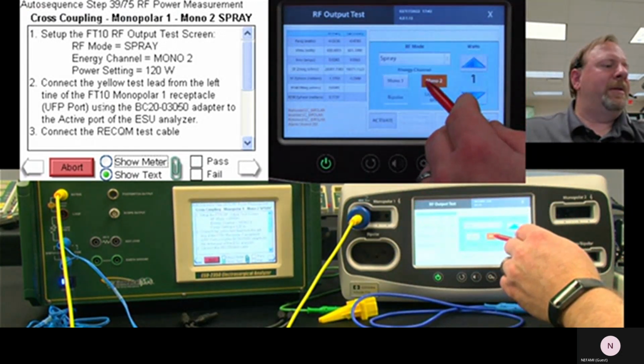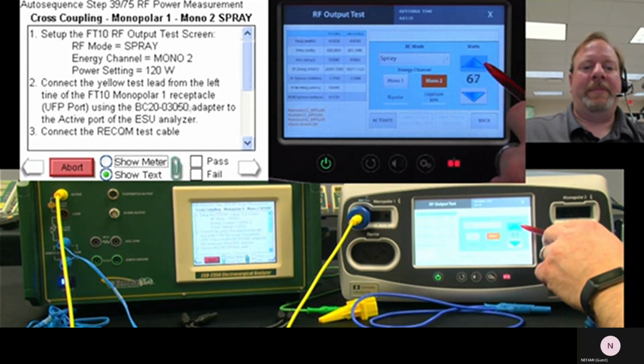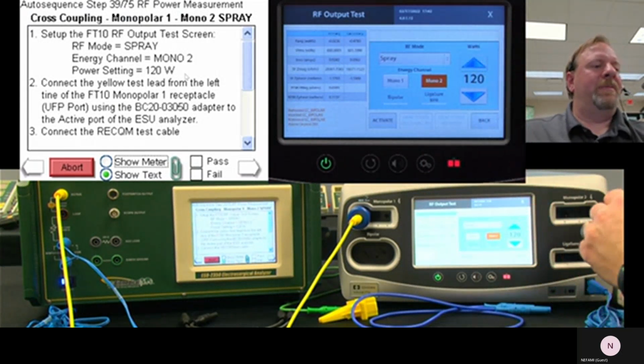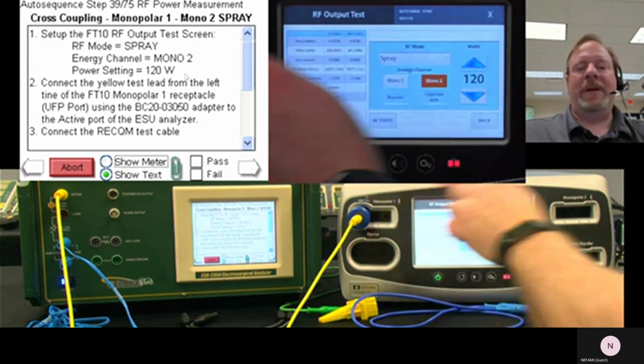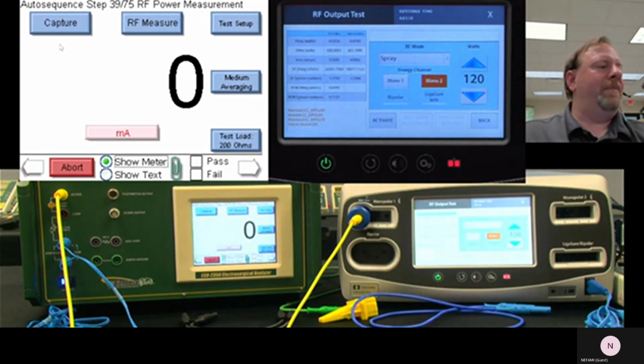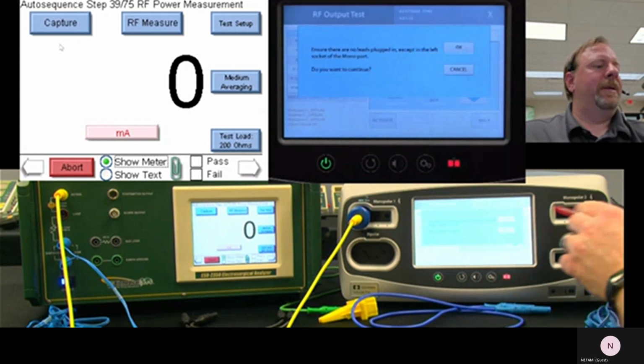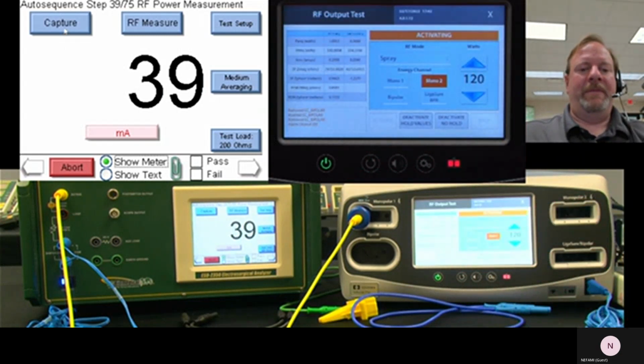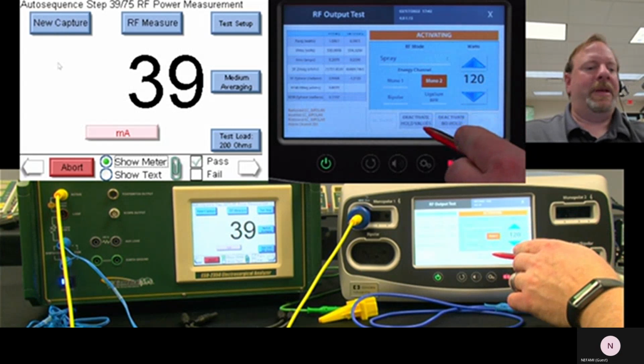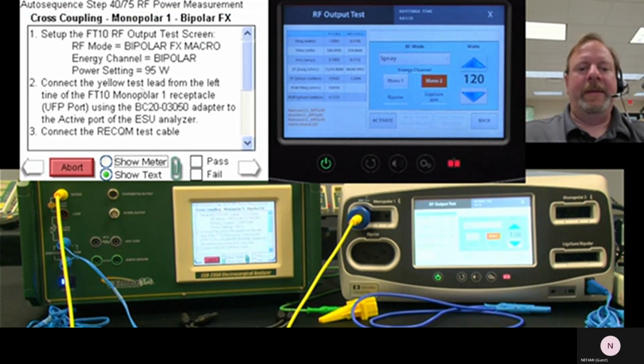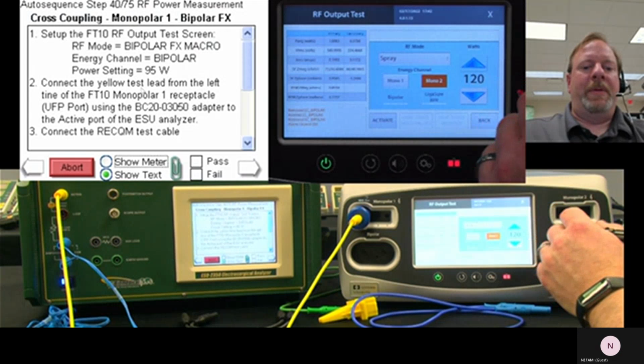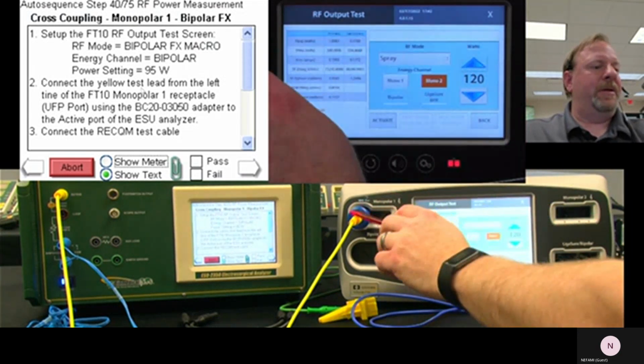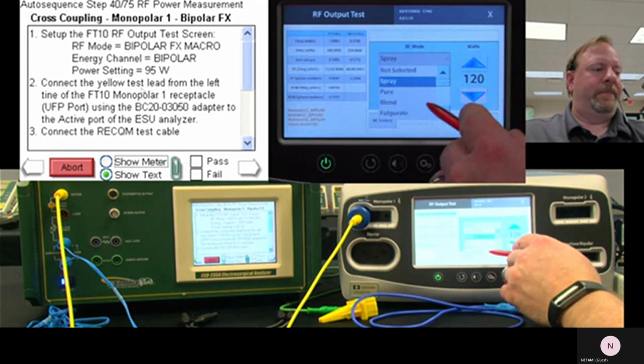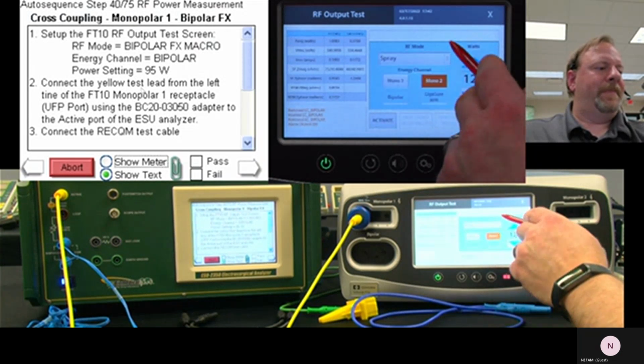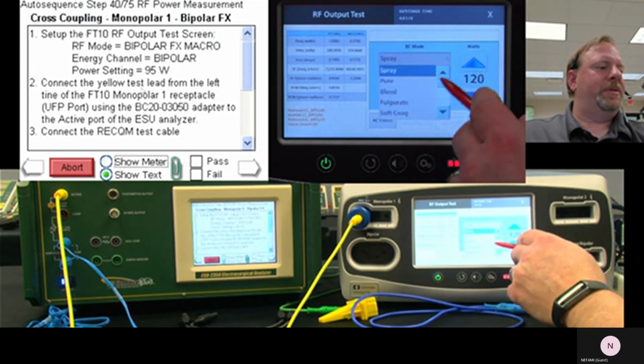So in this case, now connect to the left hand of monopolar 1. So we're staying in monopolar 1. We did pure, and now we're going to do spray. And my guess is it's going to be max power. Yep, 120 watts. So what's the maximum worst case output here? How much do I accidentally get out of the port I'm not supposed to be using? And in this case, we have 40 milliamps. And we capture that. It says it's good. Now we're going to do bipolar. So we're still measuring out here, but we're going to tell it to do a bipolar output. If I can push the button, right?